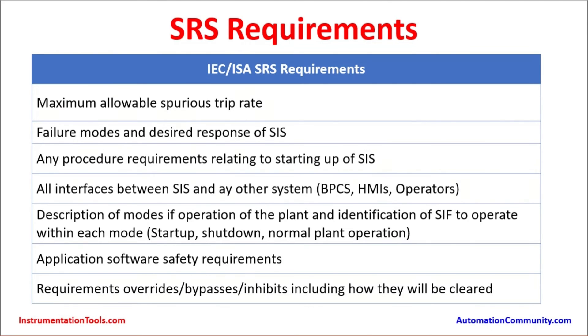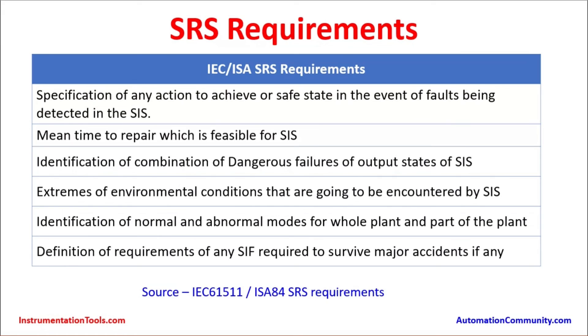All interfaces between the SIS and other systems must be specified — including the BPCS, operator HMIs, etc. Description of modes of plant operation (startup, shutdown, normal operation) and identification of SIF associated with each mode must be included. Application-specific safety requirements, requirements for overrides, bypasses and inhibits and how they will be cleared, and specification of actions to achieve a safe state in the event of detected SIS faults must all be documented.